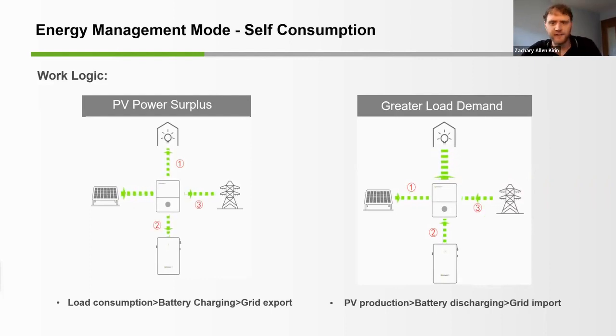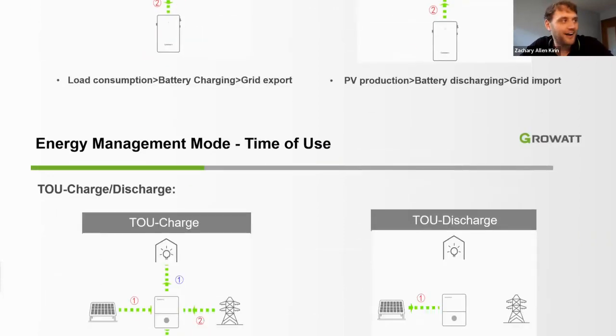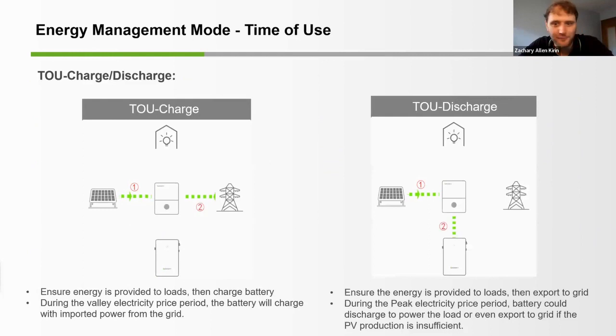These graphics here show how the load consumption is prioritized. Battery charging occurs when the load demand has been met by the solar production, and exportation to the grid begins only after the loads have been powered. During the night, consumption is handled by the battery first, and energy is only imported from the grid once the state of charge of the battery has reached its critical level. Good. I hope those slides are working properly there.